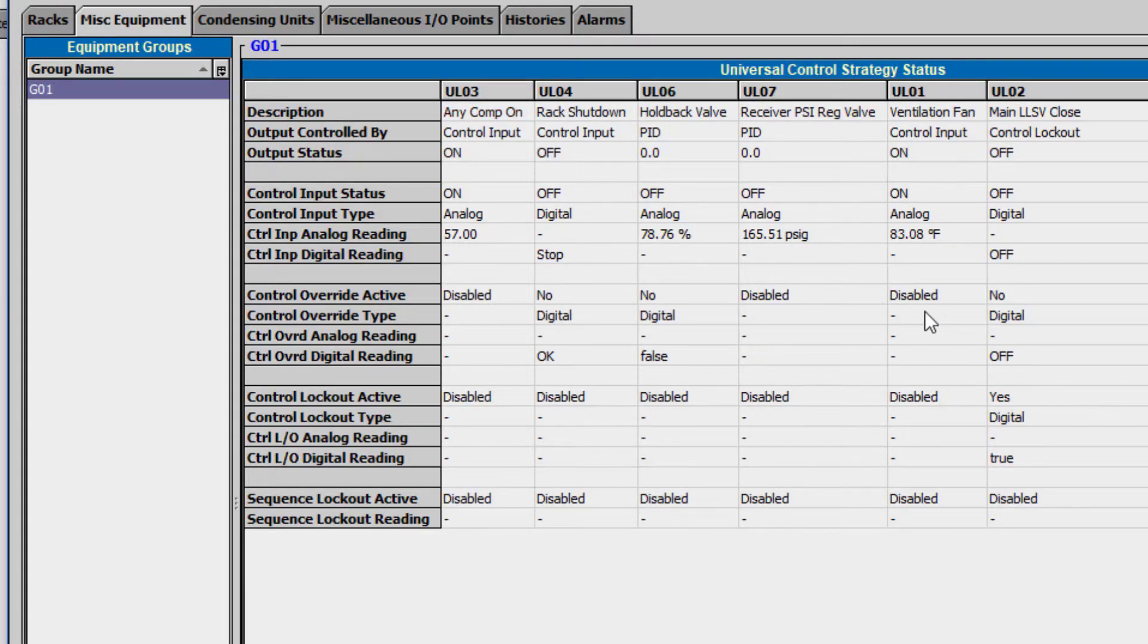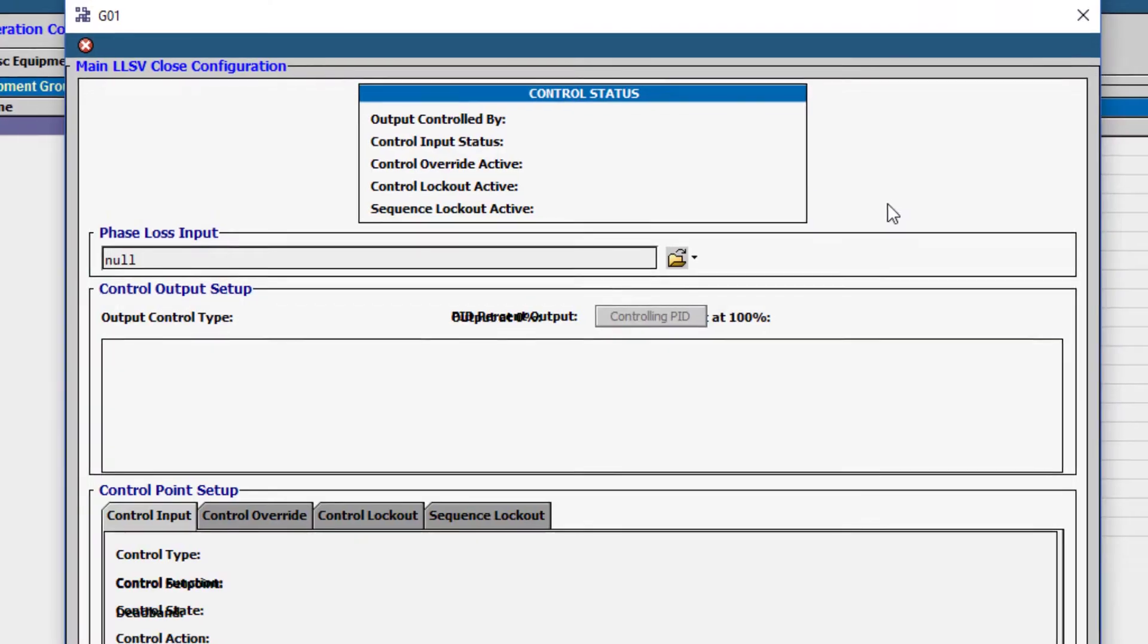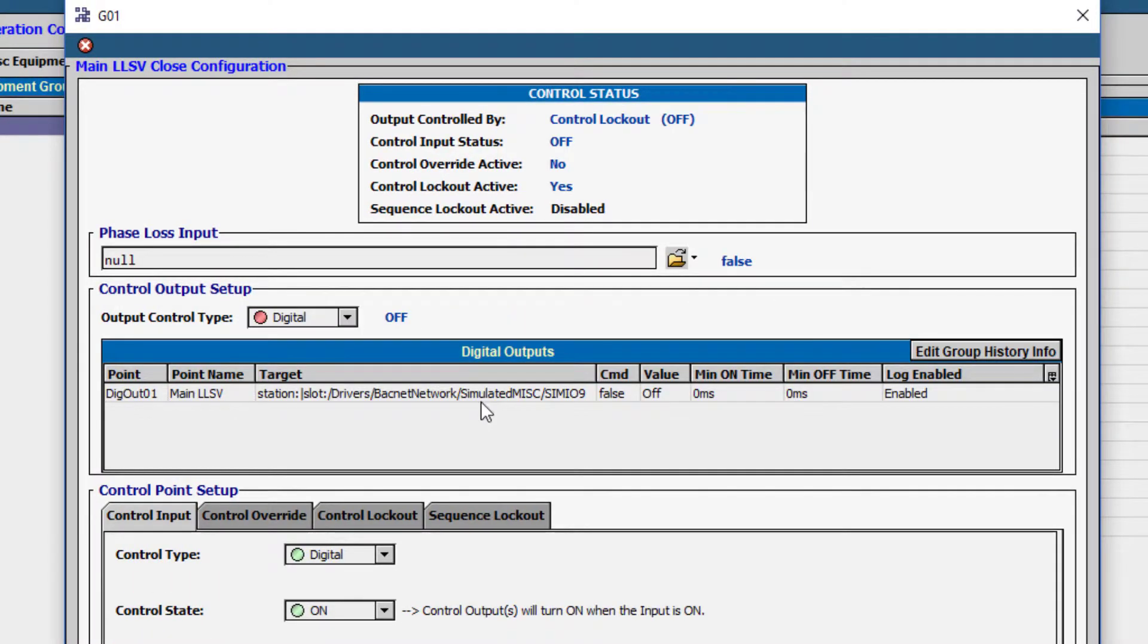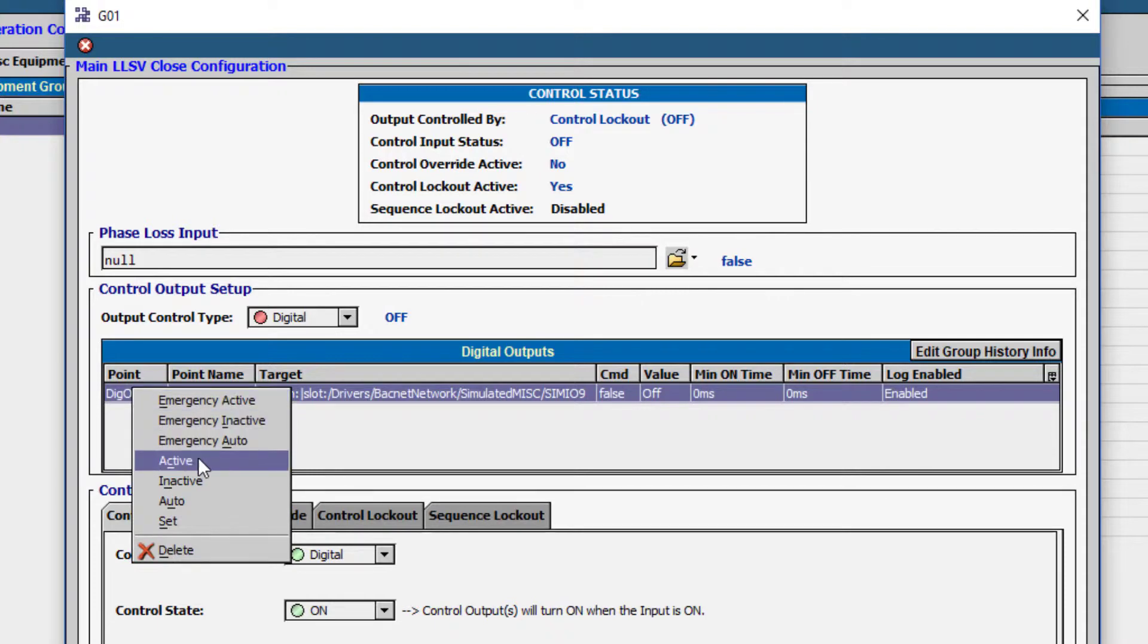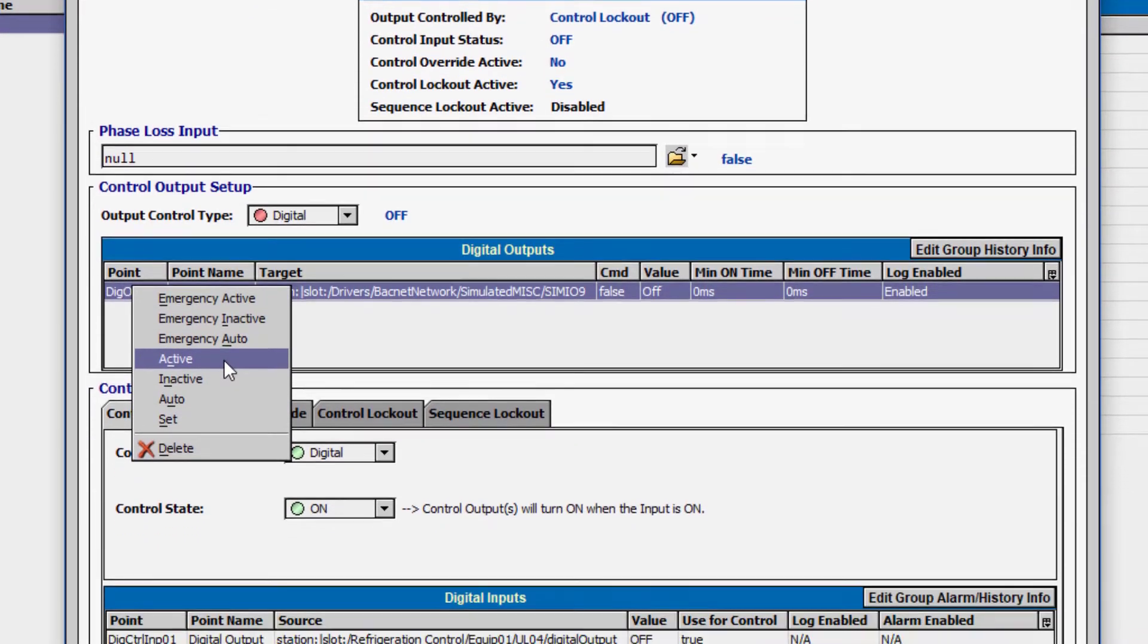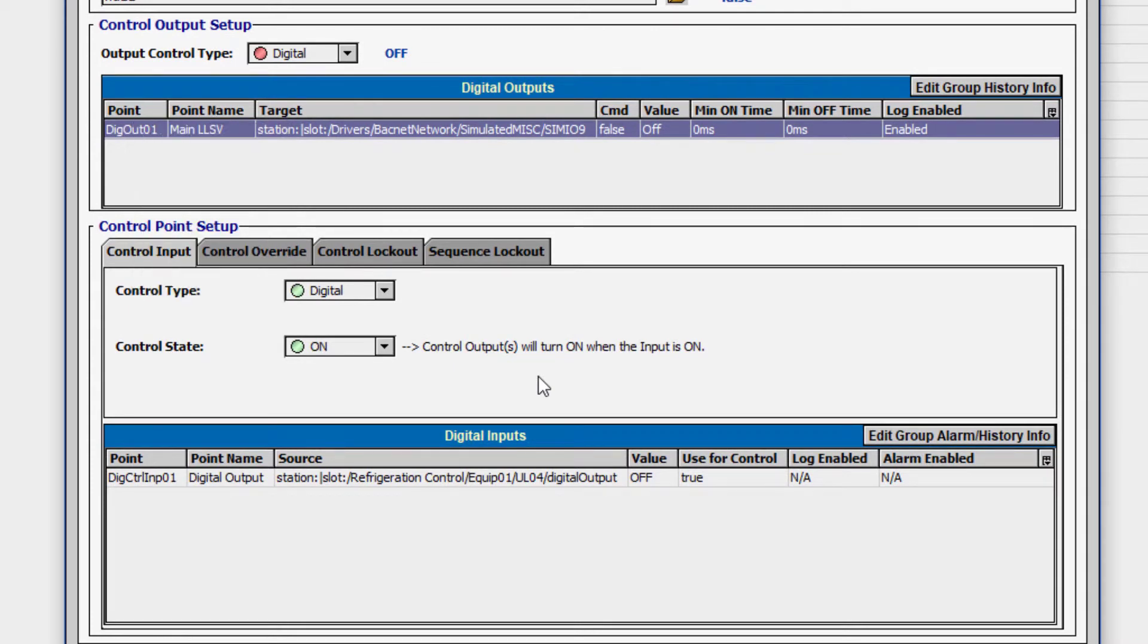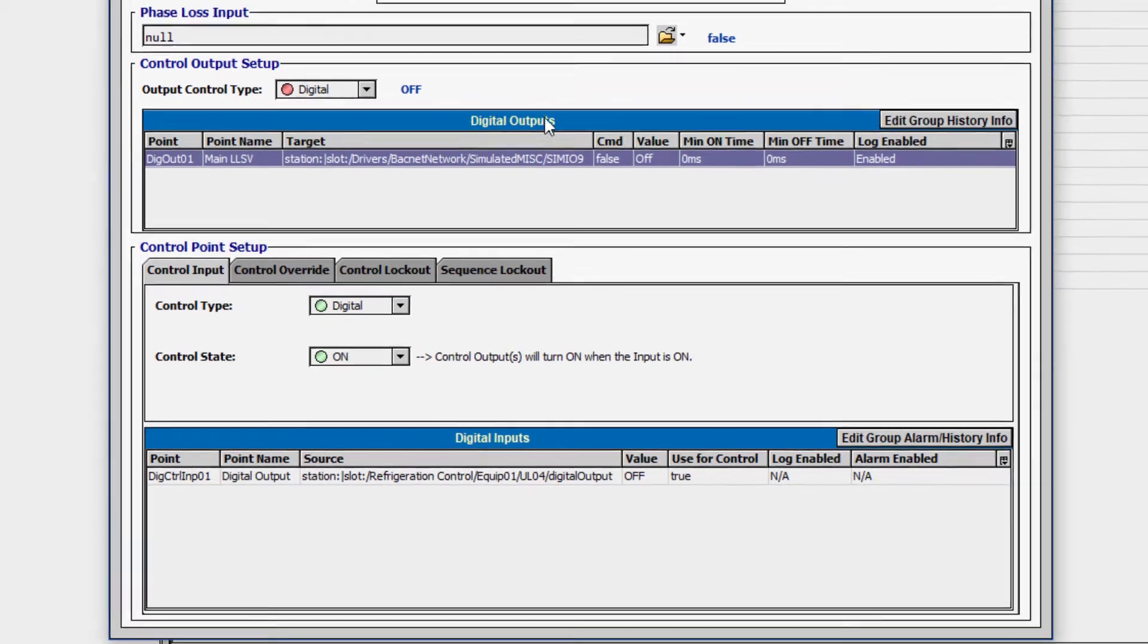Additionally, there are override options under each of the universal loads. Looking at the main liquid line solenoid valve control, we can override its output by right-clicking on the digital output in the control output setup. Even though there is a digital input we could manipulate at the bottom of this page, it is best to manipulate the output point directly.